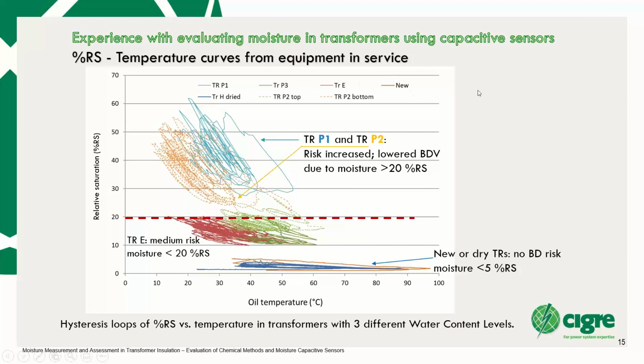And we have the next case, actually the worst case: transformers which are wet. These are two transformers. One of them, we can see the relative saturation, probe tank bottom. This is the dashed orange curve, and there is a dashed green curve which shows the same transformer, tank top. Both curves are over 20%, and we can see that the broadness of the hysteresis curve is about 20% and even higher. And one more transformer with a probe tank top. This is the blue one here, again with the same kind of evaluation criteria.